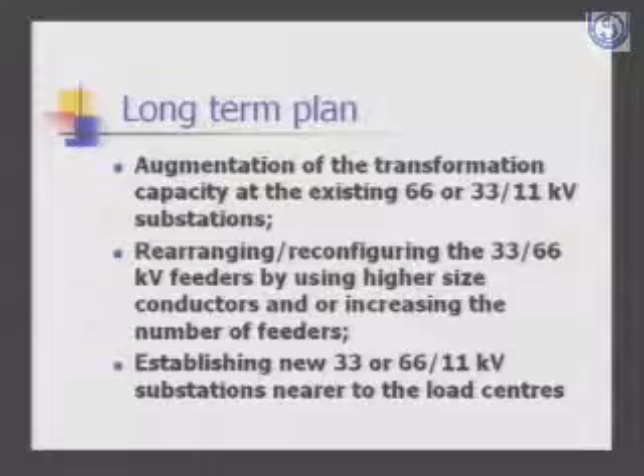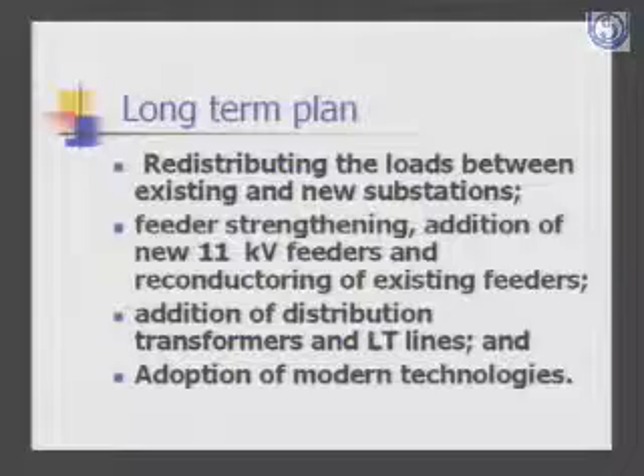Our system becomes obsolete over time, so we incorporate new technologies for increasing the quality and reliability of supply, as well as for reduction of technical and commercial losses. We incorporate HVDS systems, SF6 switchgear, aerial bunched cables, SCADA, DMS — all the technologies we can put in within a reasonable time frame. We try to include all these under the long-term measures.